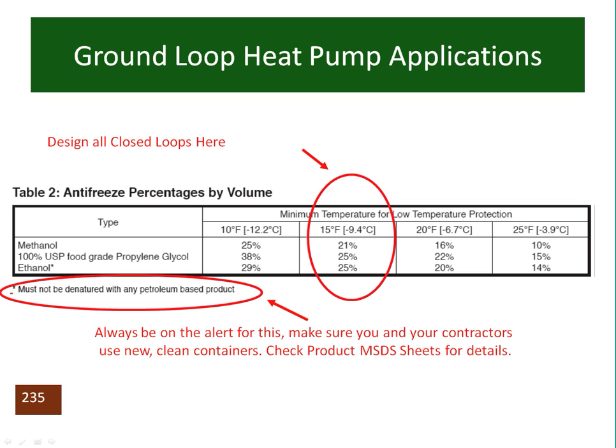In our IOM, these are the three most commonly used antifreeze solutions: methanol and ethanol, both alcohol-based fluids, as well as propylene glycol. Touching for a moment on the two alcohol fluids, those are highly flammable. They're a bit volatile. So if you're going to be utilizing it in anything but an open carport, in other words, in some kind of a structure or enclosure area, please make sure that you cut it 50% with water to take that flammability away from it. Please always use eye protection as well.